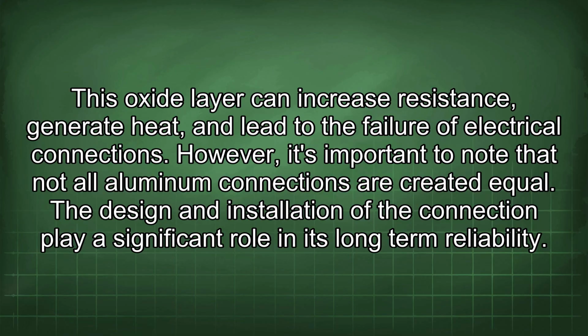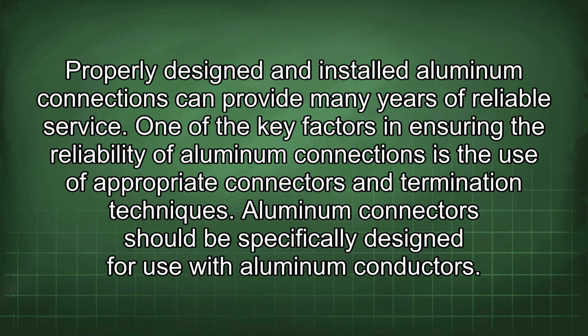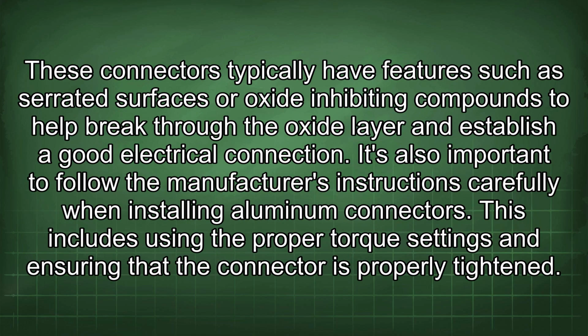However, it's important to note that not all aluminum connections are created equal. The design and installation of the connection play a significant role in its long-term reliability. Properly designed and installed aluminum connections can provide many years of reliable service. One of the key factors in ensuring the reliability of aluminum connections is the use of appropriate connectors and termination techniques. Aluminum connectors should be specifically designed for use with aluminum conductors. These connectors typically have features such as serrated surfaces or oxide-inhibiting compounds to help break through the oxide layer and establish a good electrical connection.